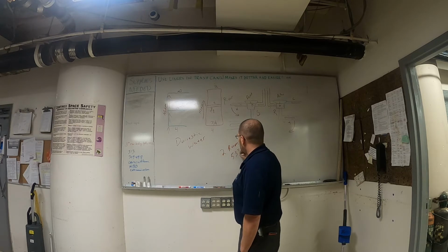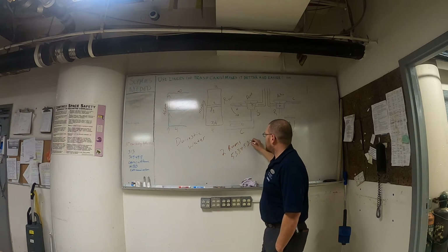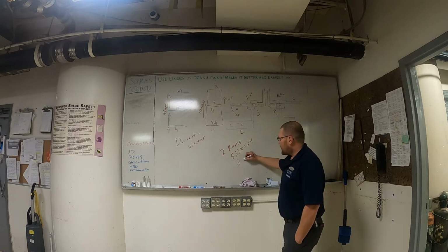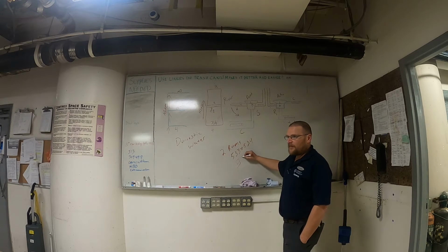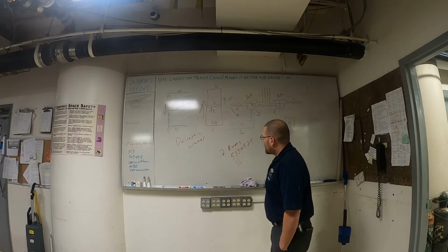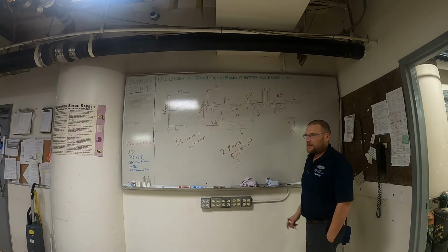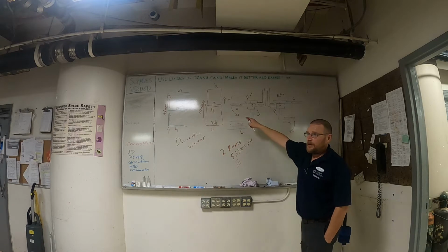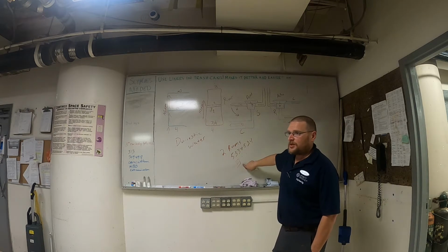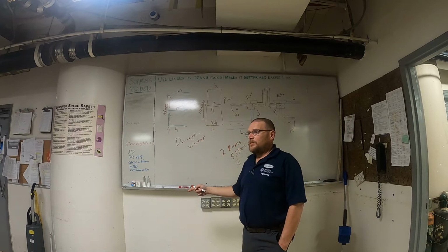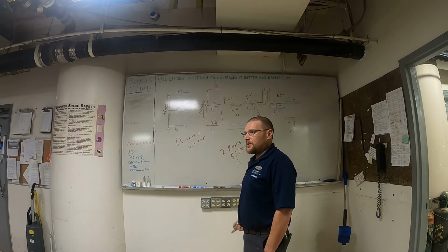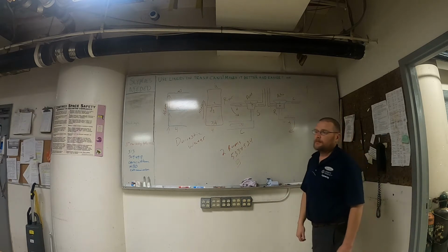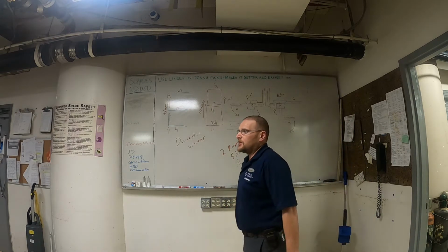Room 533 and 534 have a different thermostat. They have two what they call Belimo valves in it. Basically, these two Belimo valves are going to do the same thing as we're doing here, except this is going to work towards this one thermostat. So each room will be its own individual area. We'll basically be turning a 2-pipe system into a 4-pipe system, so you can have heating and cooling in the same room.